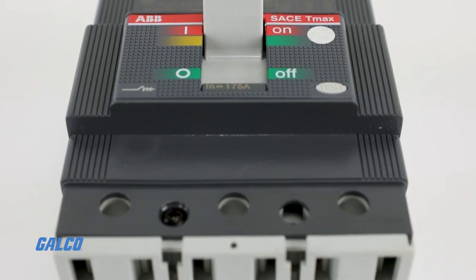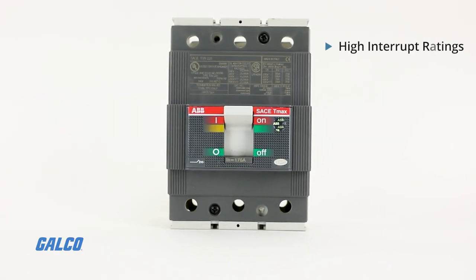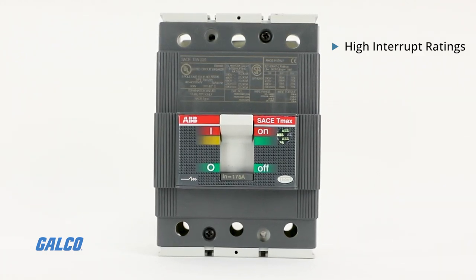Lines can be fed into either end of the breaker with no derating of performance characteristics. And high interrupt ratings, up to 150 kiloamps interrupt capacity at 480 volts AC.